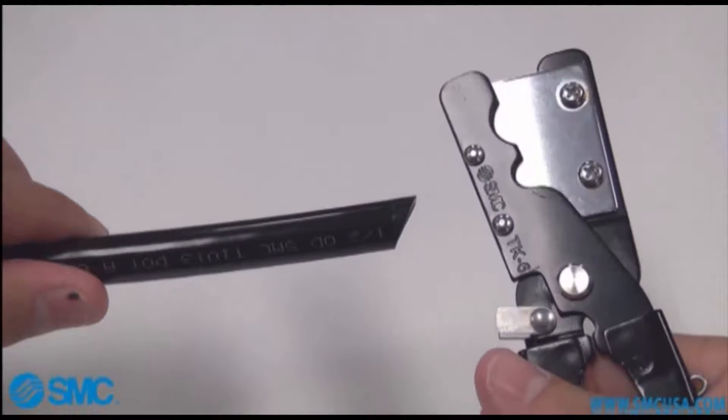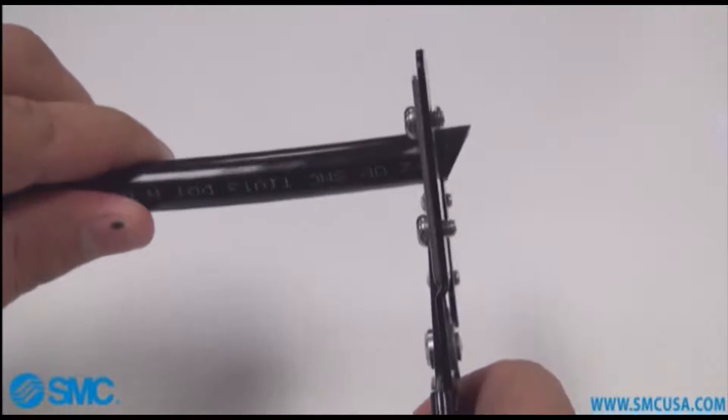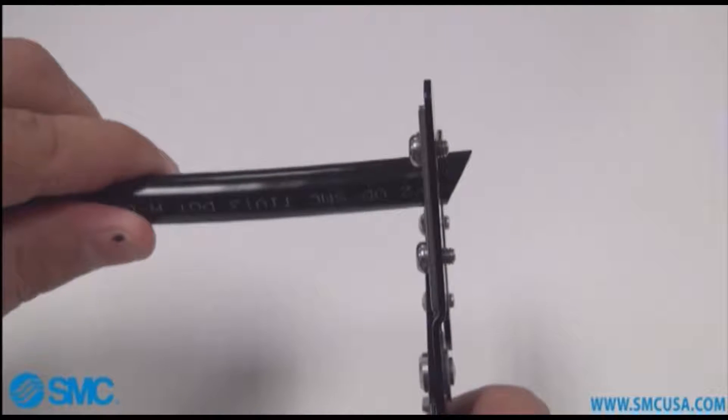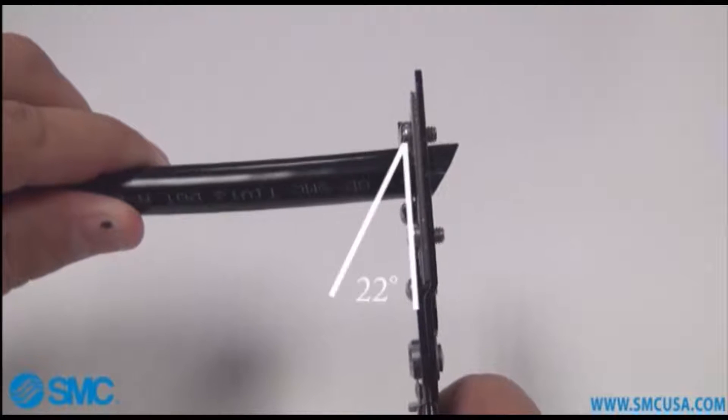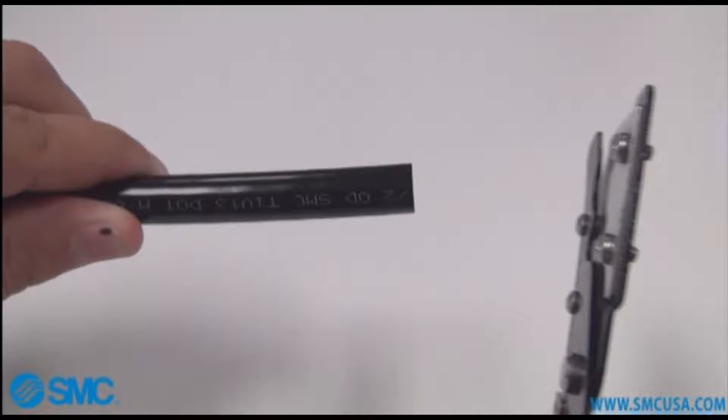Take a piece of the tubing and position it into the cutters. Pay close attention that the tube is square to the cutters. The maximum degree off of square is 22 degrees. Zero degrees is obviously the most ideal cut.